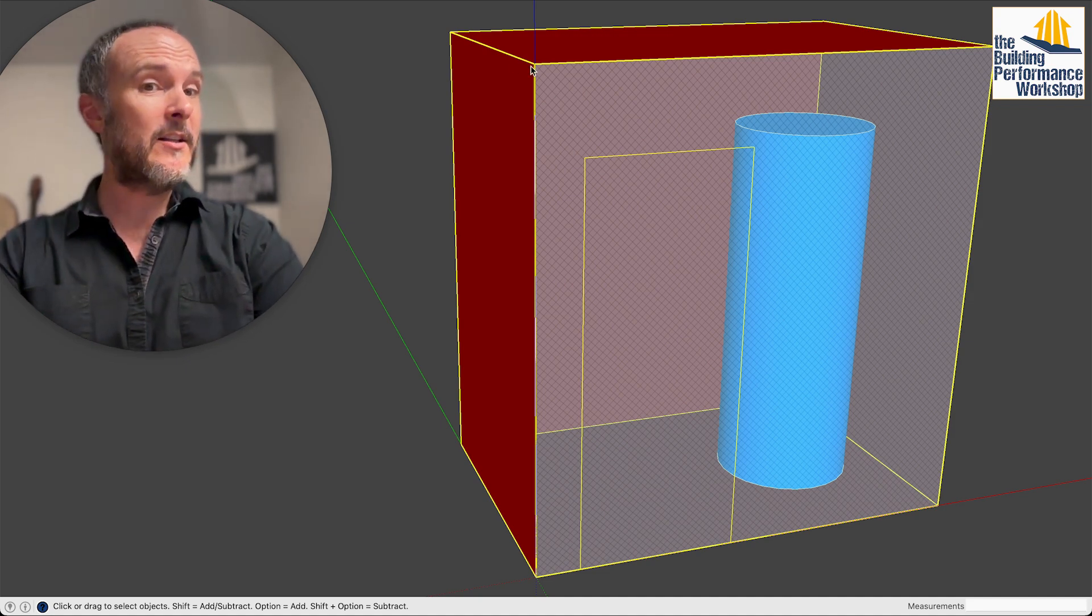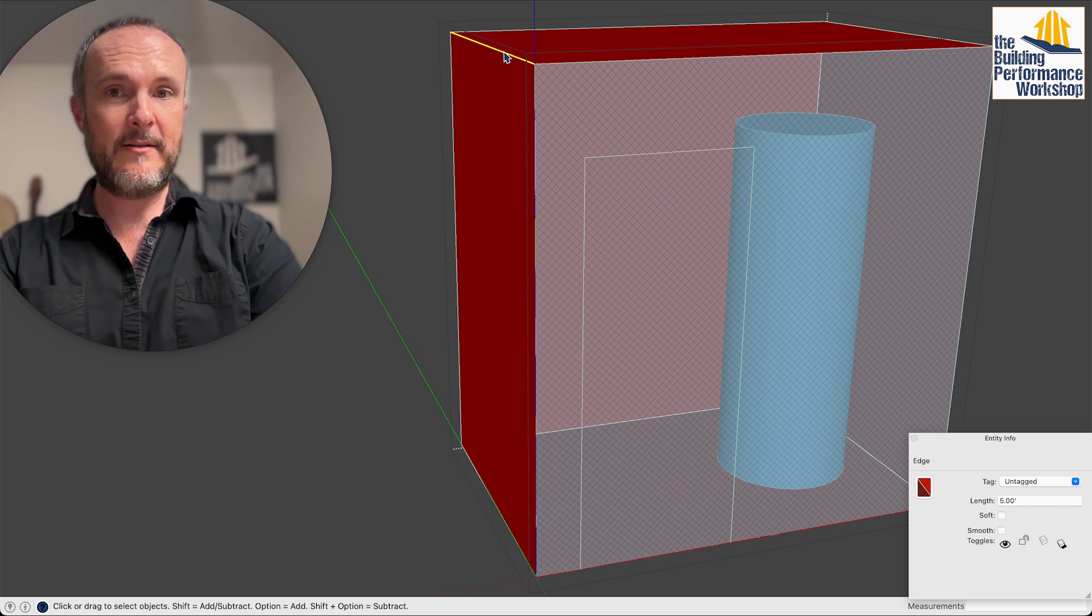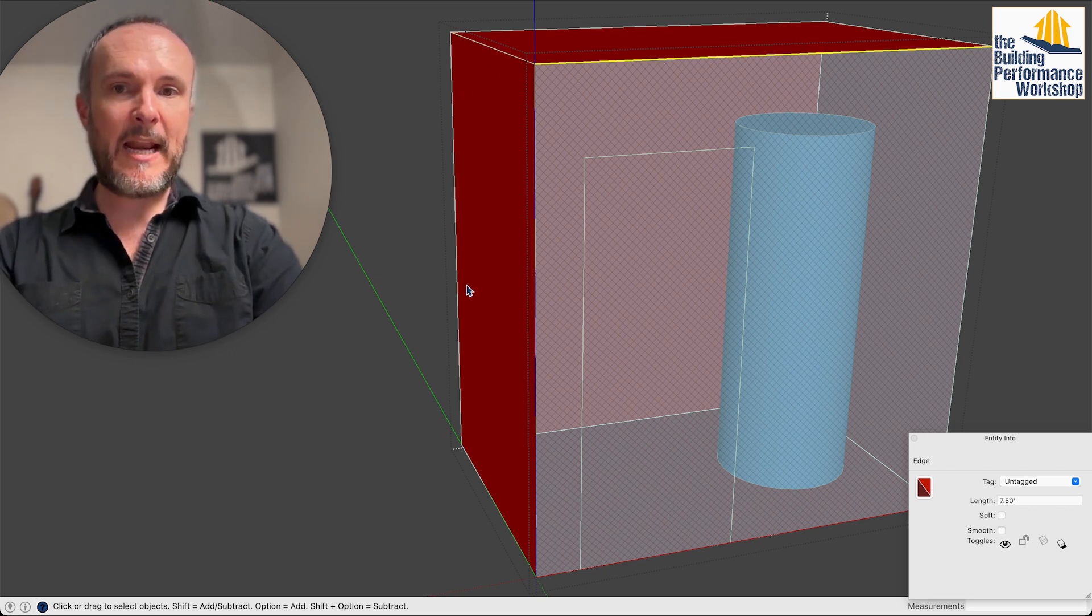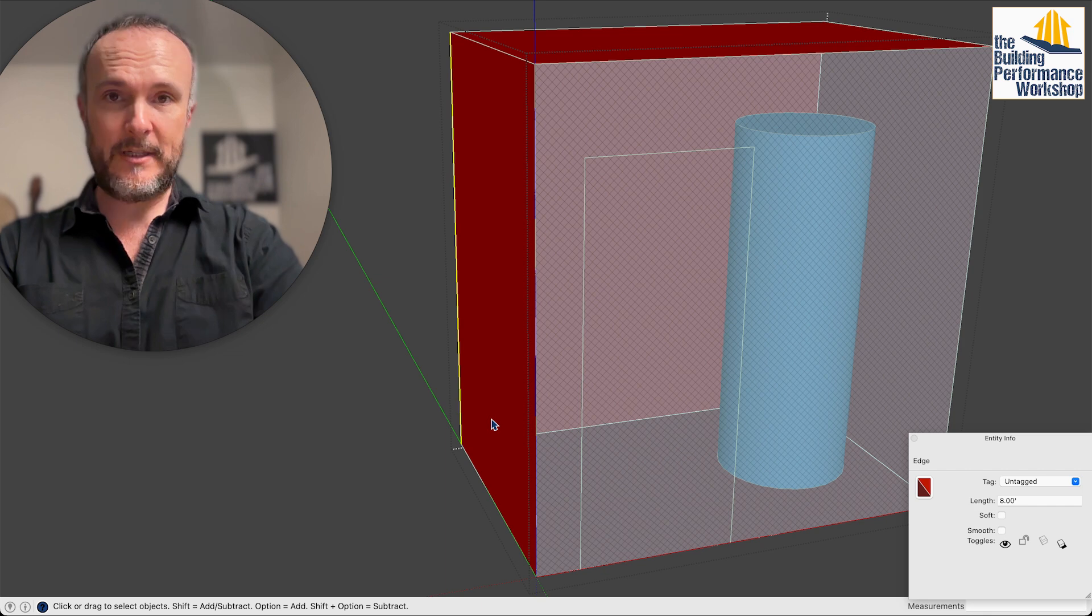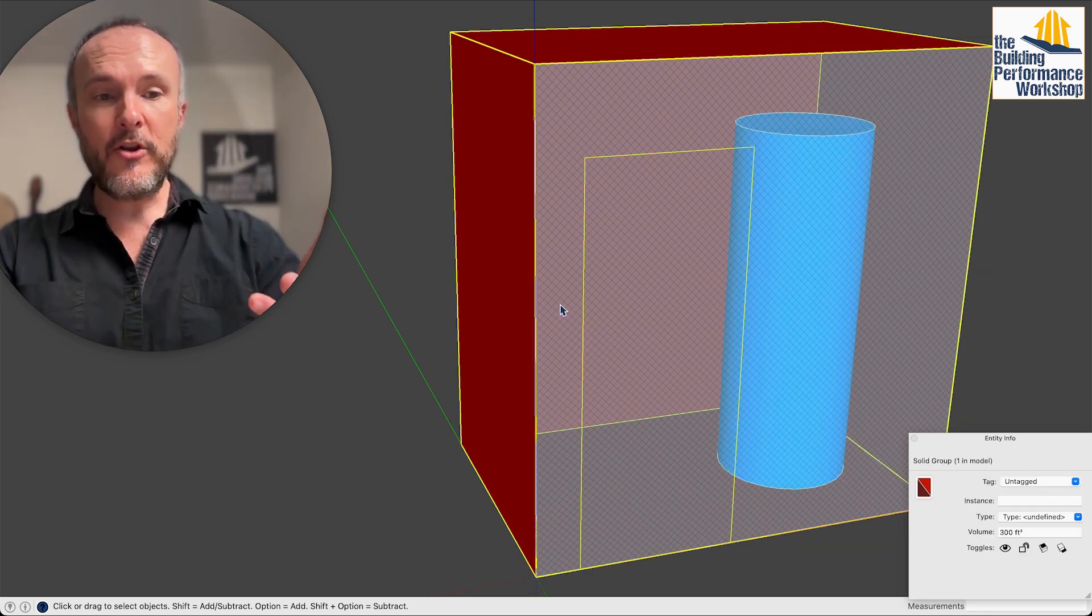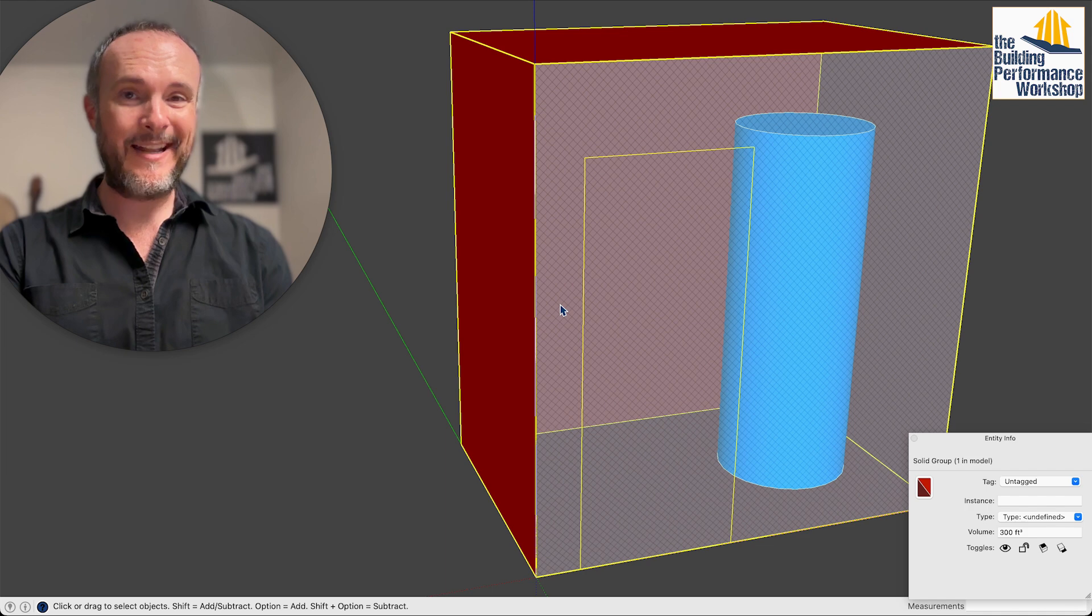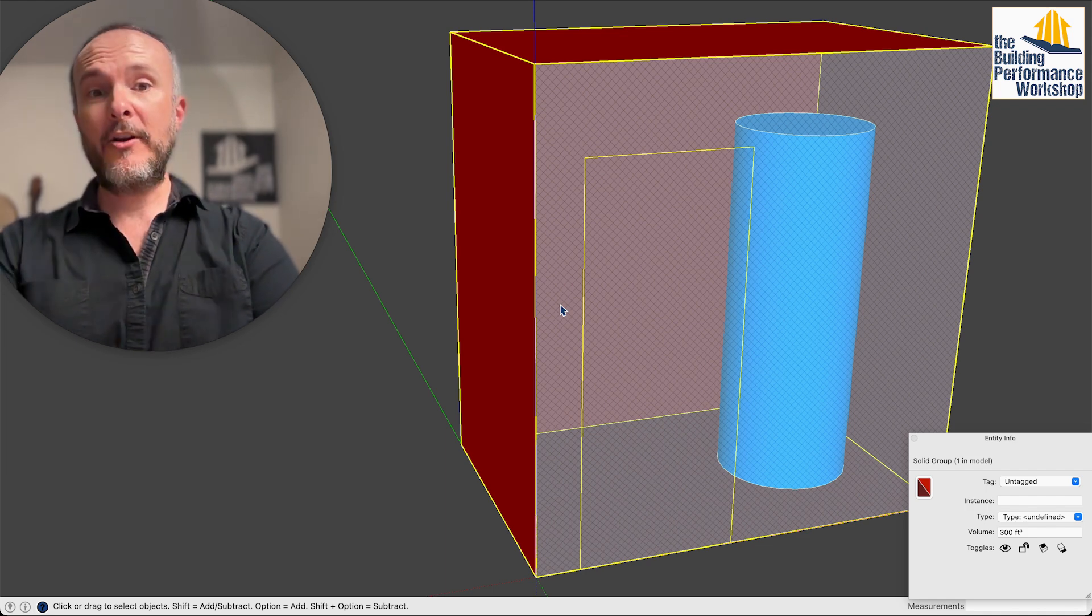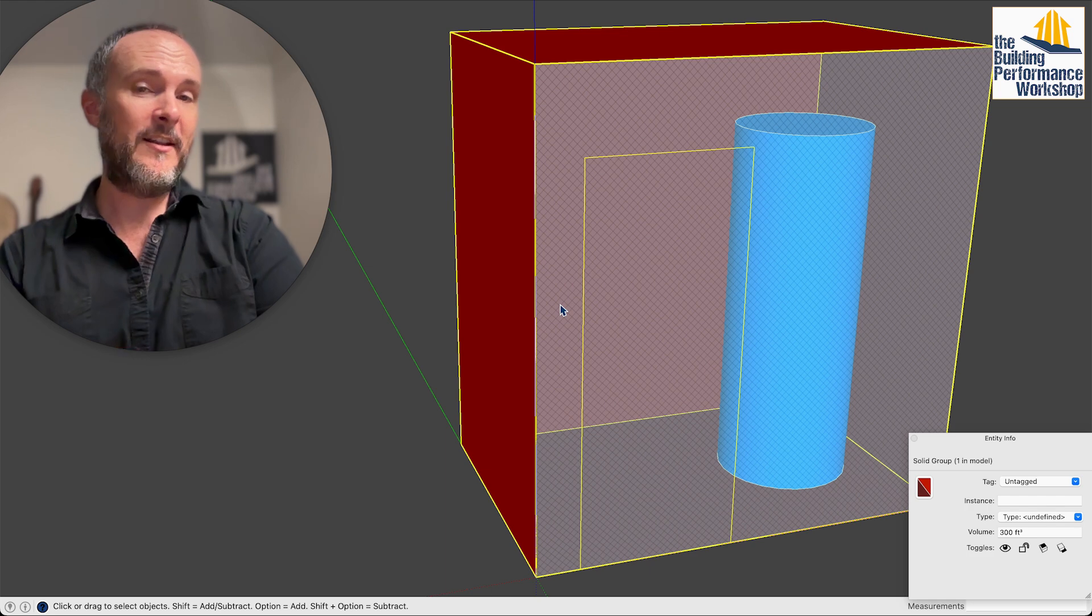So let's look at this little room that I've got your heat pump water heater in right here. This room is five feet deep, seven and a half feet wide, eight foot ceiling. So that totals out to a volume of 300 cubic feet. That's less than half of what they want you to have. So they're going to say this thing can't be installed in there.